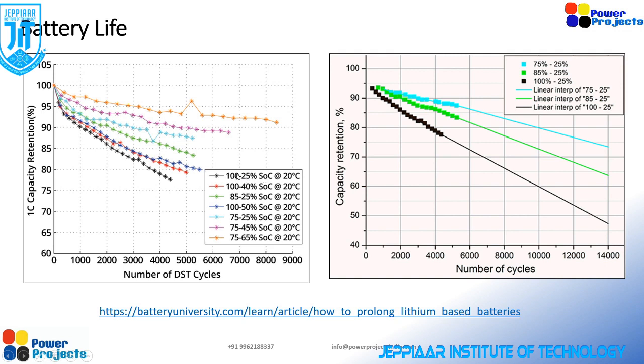What does that mean? The maximum SOC is 100 and the minimum SOC is 25, at a 20-degree ambient temperature. The minimum SOC is maintained at 25, and the ambient temperature is maintained at 20 degrees. When the SOC reaches 25, you have to charge it up to 100%, and after 100% it starts discharging. If it is discharging and comes down to 25% SOC, again you have to charge. So with that, for 4000 cycles, how much capacity it can retain is available from this graph. Approximately when the battery reaches about 70% of its retention capacity, then you can call that battery life over.